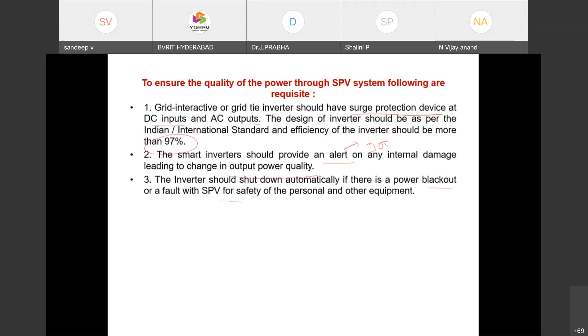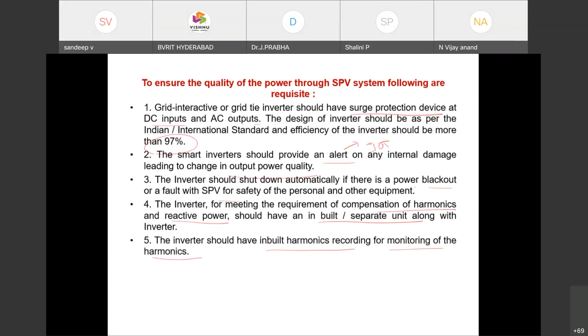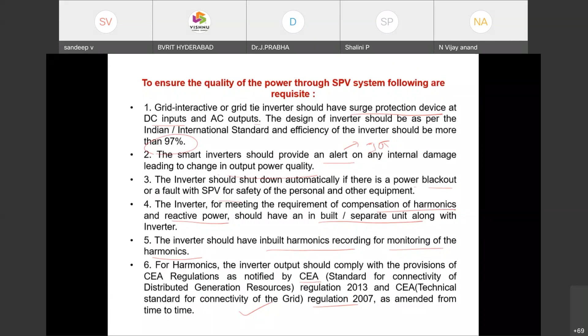Next, any compensation methods required for harmonics or reactive power should be taken care of, as inbuilt or as a separate unit along with the inverter - the grid will not take care of this. The inverter should have inbuilt harmonic recording and monitoring, with a display system. And regarding harmonics, we need to follow the compliance of the Central Electricity Regulations 2013 and 7, as they specified.